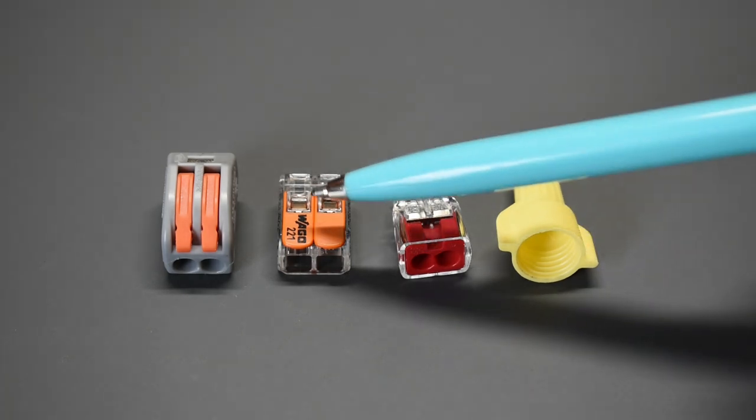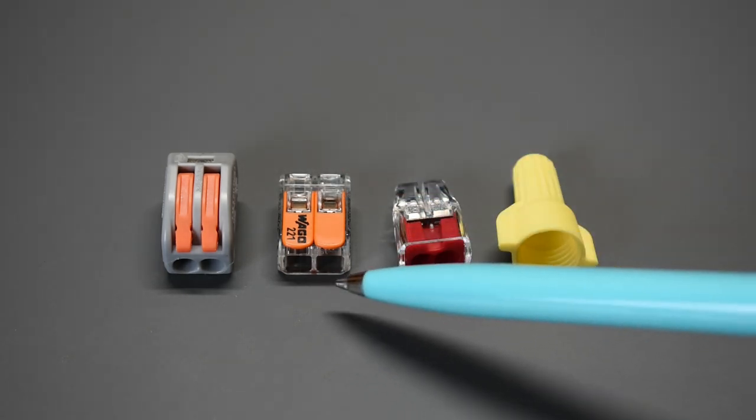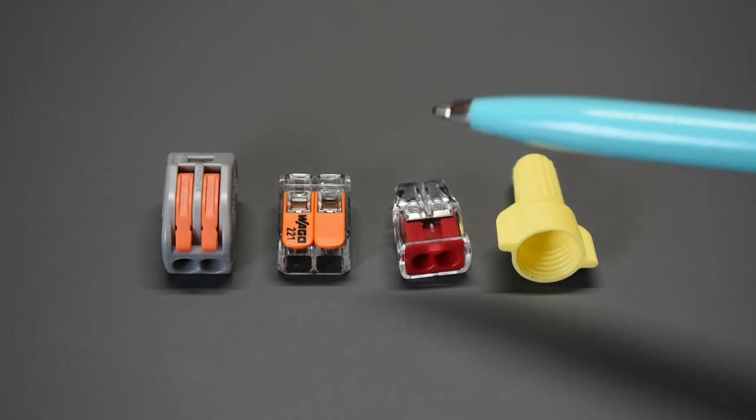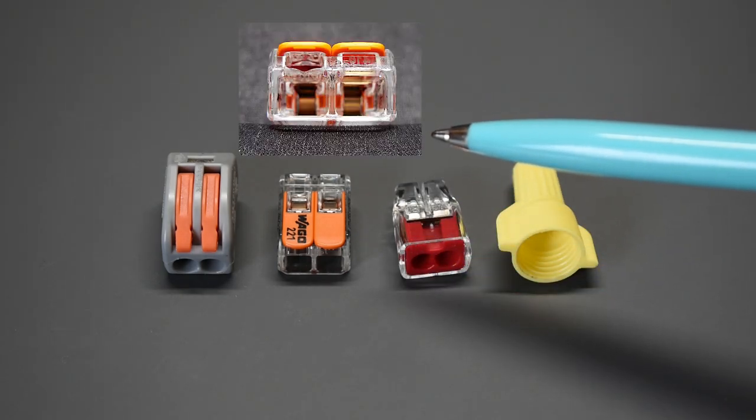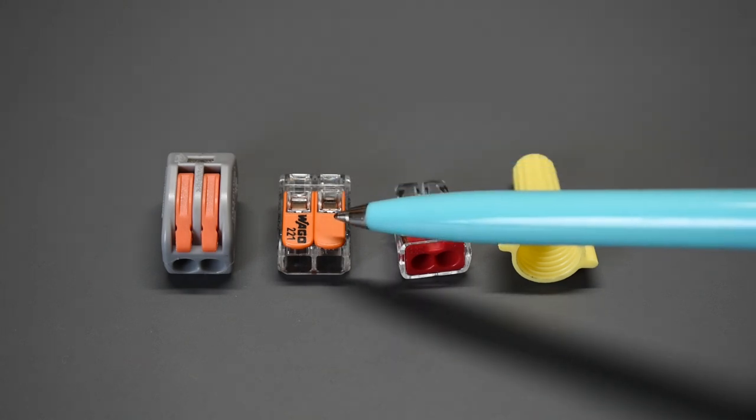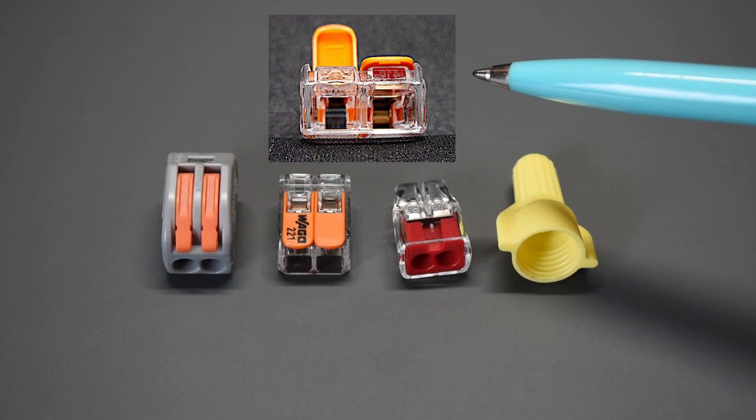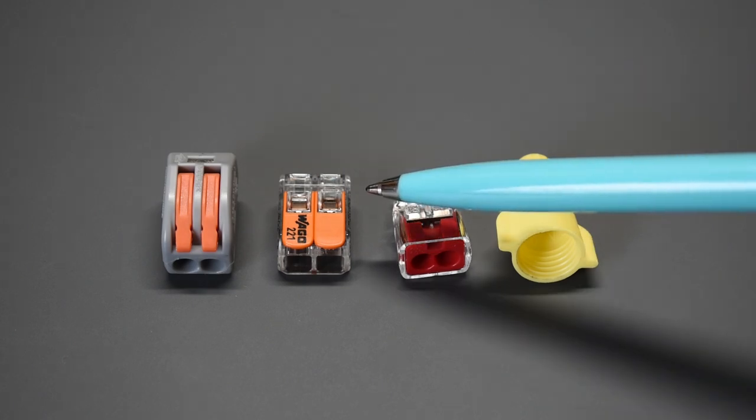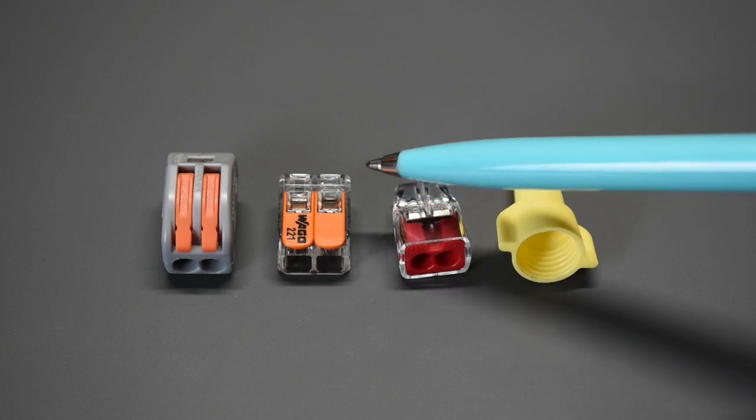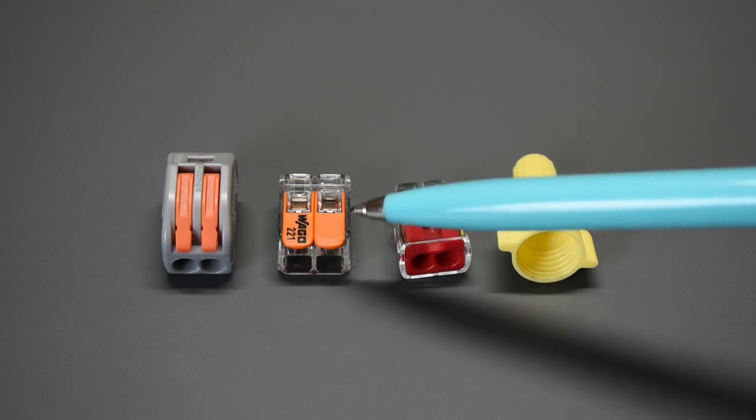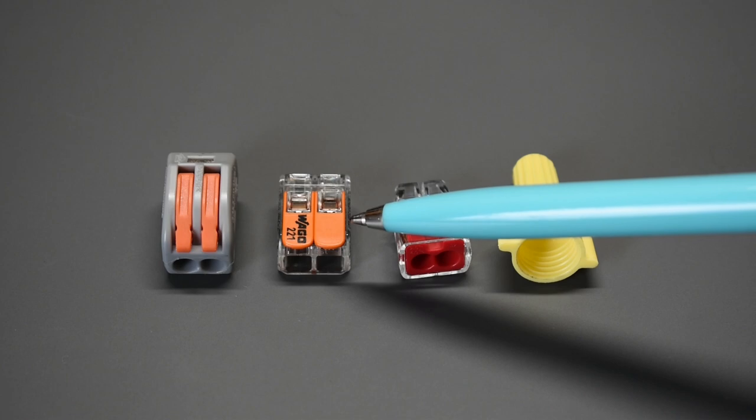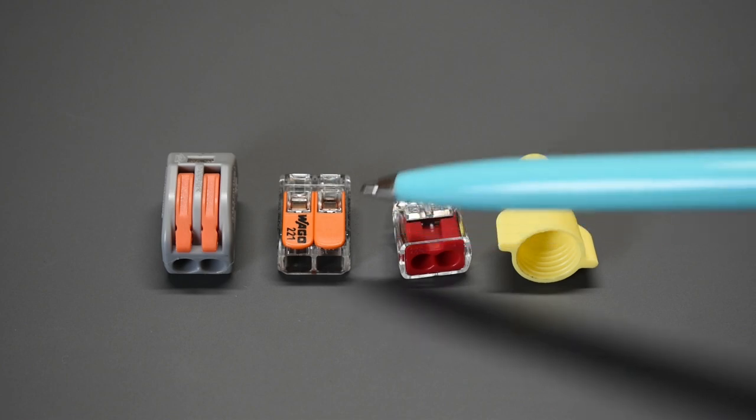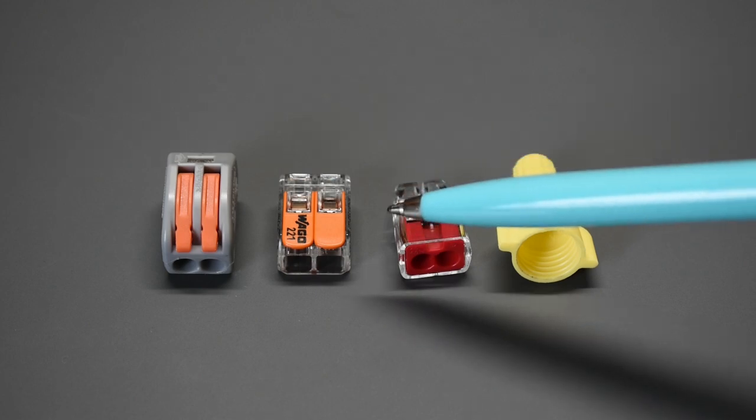Now with the Wago 221 connector, you can see there's two openings here. When you look inside, it looks like there's two doors that are down, almost like a brass color. And when you lift the lever up, it opens. And in this image, you can see one is open, one is closed. You would strip a half inch of insulation, 12 millimeters, and once it's all the way into the connector, you would take the lever and push it all the way down so it's flat. Once it's in the down position, it's locked, and all the tension on that metal inside the connector is now placed on the conductor.